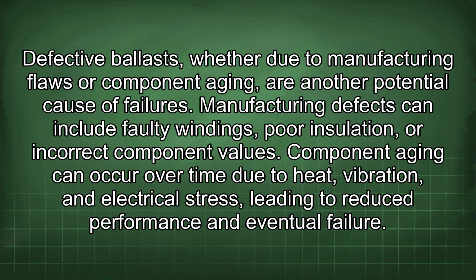Defective ballasts, whether due to manufacturing flaws or component aging, are another potential cause of failures. Manufacturing defects can include faulty windings, poor insulation, or incorrect component values. Component aging can occur over time due to heat, vibration, and electrical stress, leading to reduced performance and eventual failure.